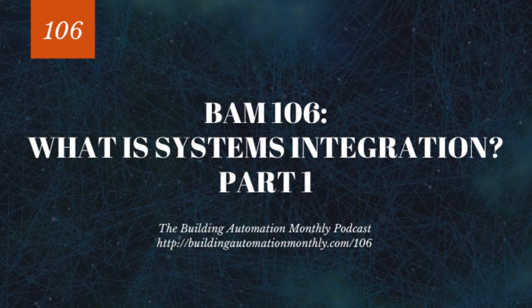But then you've also got to say to yourself, how am I going to pull this stuff in? And this is where, once again, you've got to know what you're doing. You've got to know the four-tier architecture of a building automation system: servers, supervisory devices, field trunks of field controllers, and I/O. And then you're going to be putting a break in between that supervisory server layer. But you also have to realize that if you break that, there might be a break in the logic in the server.